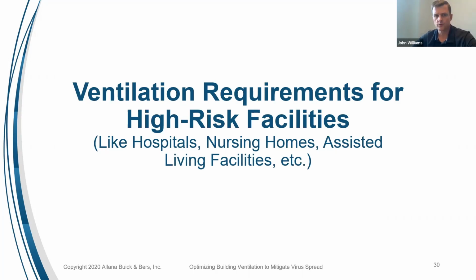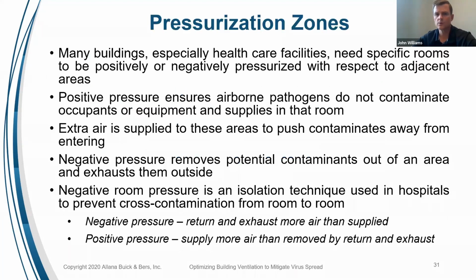We wanted to touch base on a few things that have to do with some high-risk facilities, whether it's hospitals, nursing homes, assisted living care facilities. And when we talk about these, we're really concerned about pressurization zones. Now, we have pressurization zones in other commercial buildings, whether it's restrooms or kitchens, but these are especially critical when we get into our assisted care facilities. And the reason why is because we're trying to contain and prevent the movement of viruses and microorganisms throughout the building. So what we do is we create positive and negative zones to control the airflow and therefore contain our contaminants. So a positive zone is going to prevent contaminants from entering, and a negative zone is going to exhaust contaminants out and prevent them from spreading.